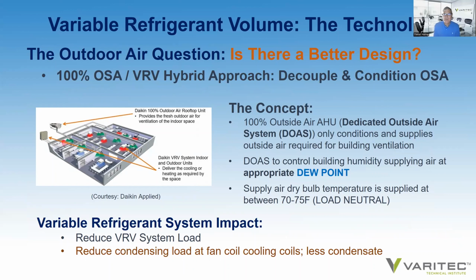So the concept is to provide a 100% outside air unit or dedicated outside air unit that only conditions the outside air. It is completely decoupled from the refrigerant system. One of the advantages of handling the outside air is you take care of the humidity of the outside air at the DOAS unit. It doesn't have to be addressed at the variable refrigerant indoor air handler. And then you supply load neutral air of 75 degrees that has been dehumidified. So we'll look at how you do that shortly.